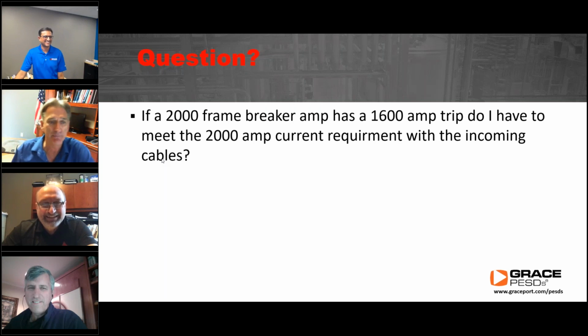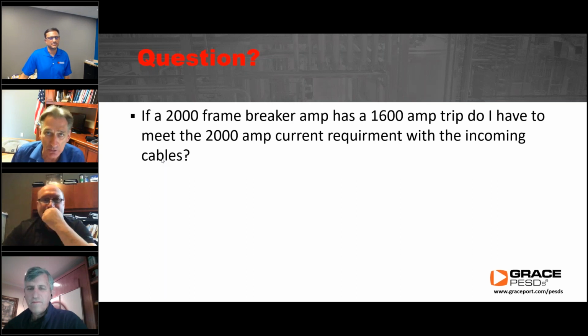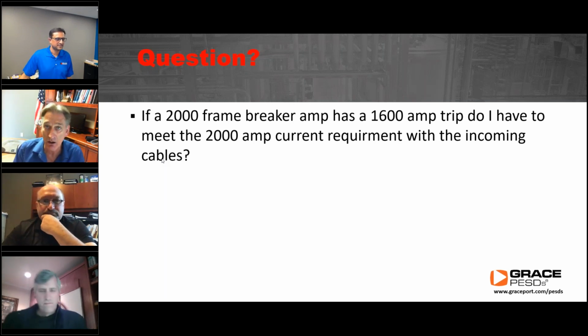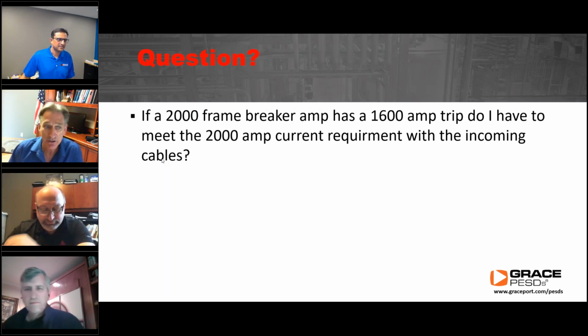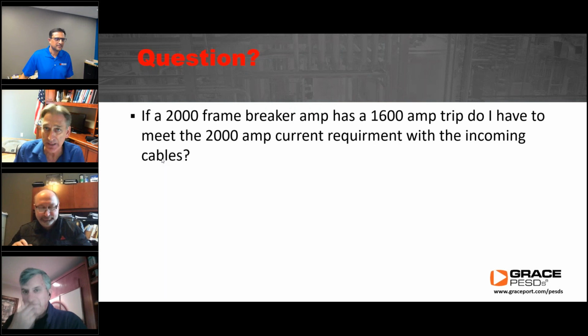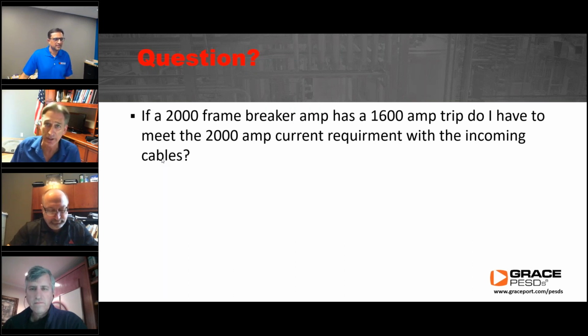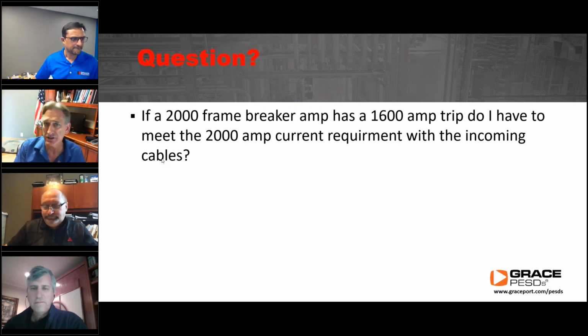All right, back to the question that I was given here. If a 2000 amp frame breaker has a 1600 amp trip, and now I'm assuming it is an adjustable trip circuit breaker. It could be a modular type with a specific module installed, but let's look at what the National Electrical Code says. The NEC in Article 240, which is overcurrent protection, 240.6(A) talks about standard size fuses and circuit breakers, and there's now a Table 240.6(A) that gives us standard size fuses and circuit breakers, of which we know most of these in that list. We know almost all of them, but let's look at B and C.